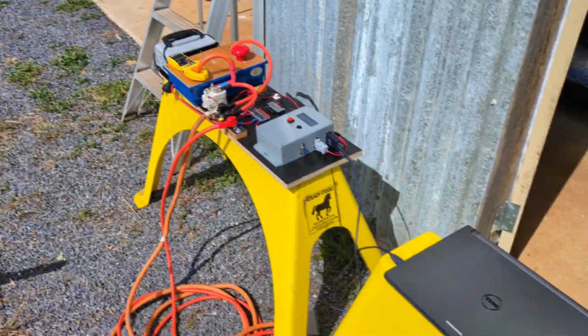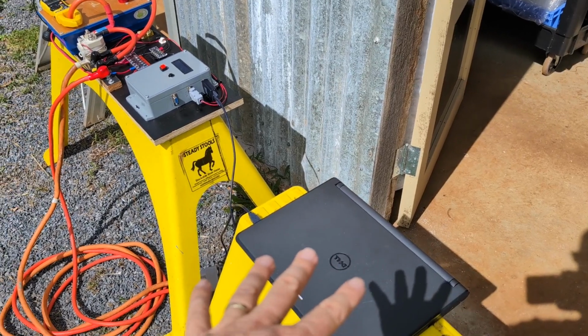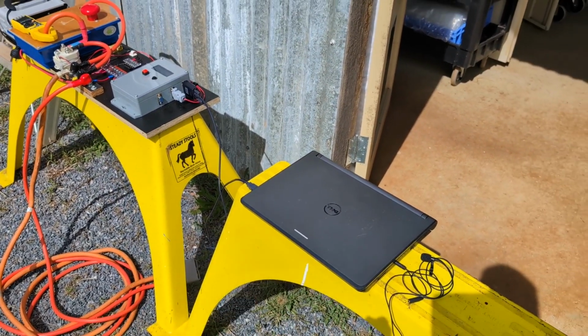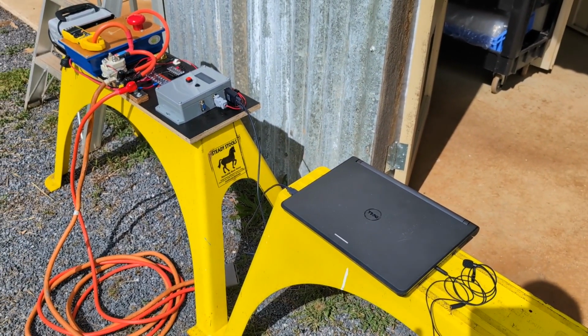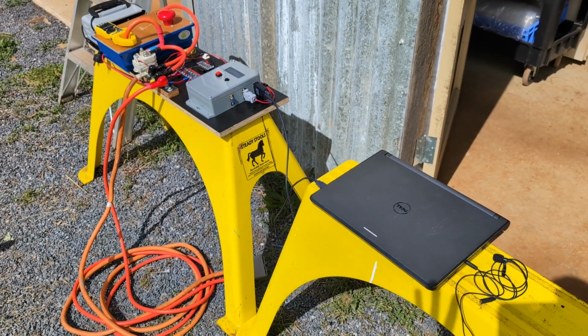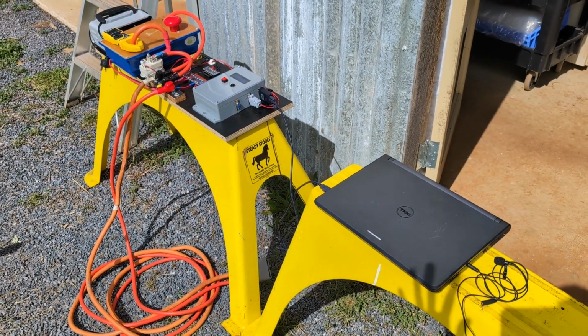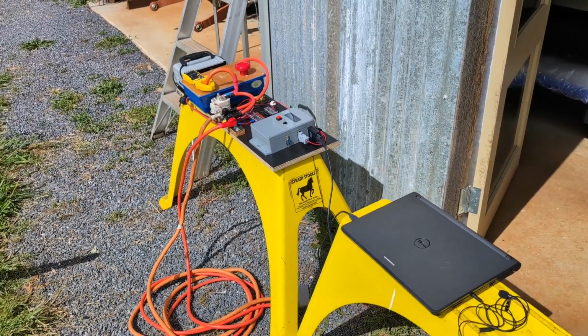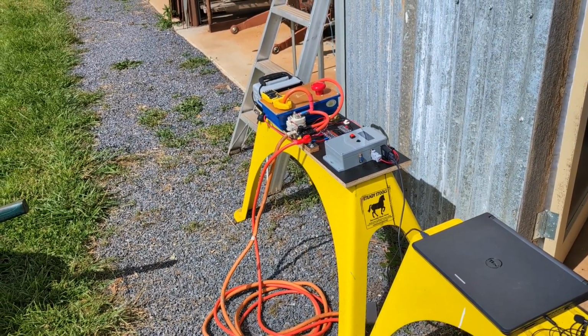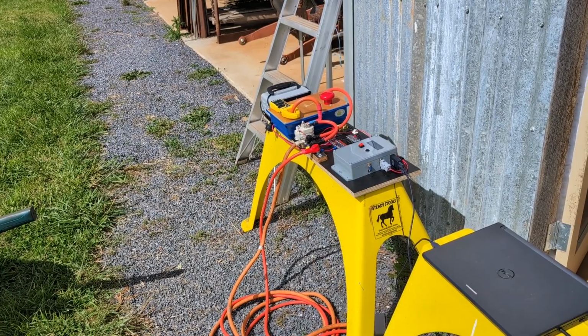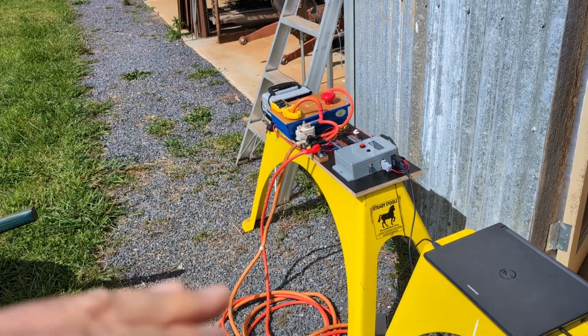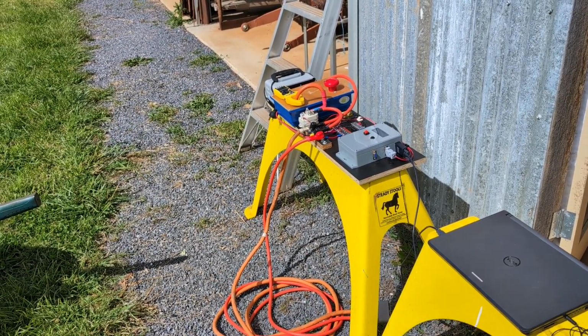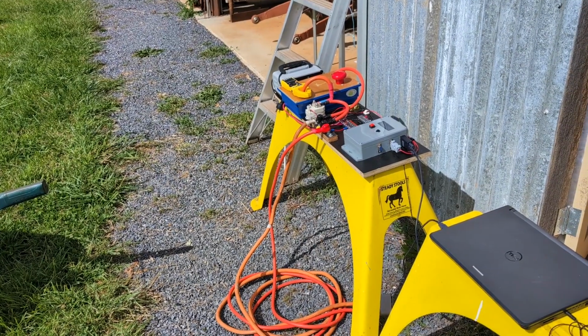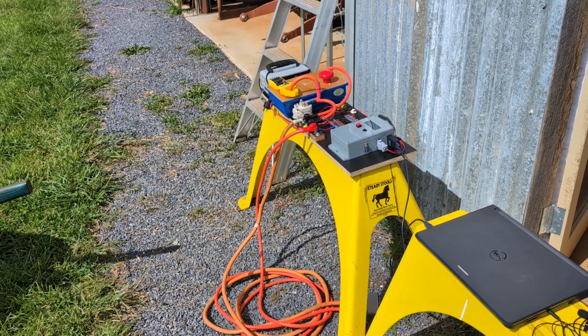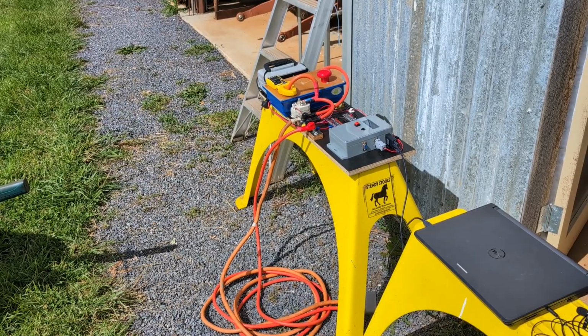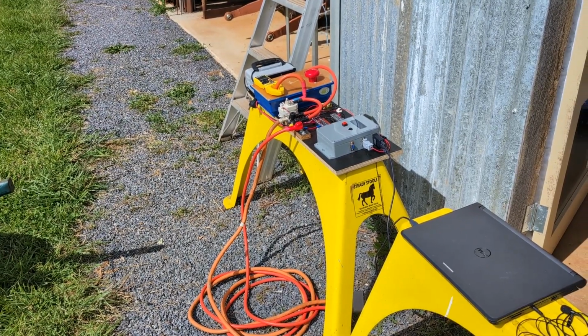I'll also be monitoring with the computer, recording each cell voltage once a second or so, and that's how I'll tell the minimum voltage of each cell. So what I want to know is the resting voltage and then the lowest voltage that any cell got to within that pack. If one of those cells got to a lower voltage than the rest of them, then I might start to be concerned.